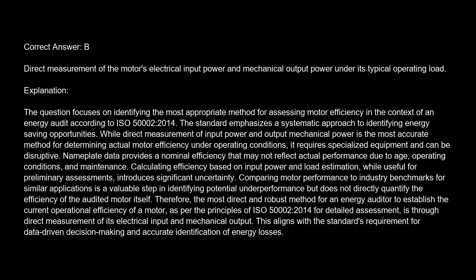The standard emphasizes a systematic approach to identifying energy-saving opportunities. While direct measurement of input power and output mechanical power is the most accurate method for determining actual motor efficiency under operating conditions, it requires specialized equipment and can be disruptive. Nameplate data provides a nominal efficiency that may not reflect actual performance due to age, operating conditions, and maintenance.